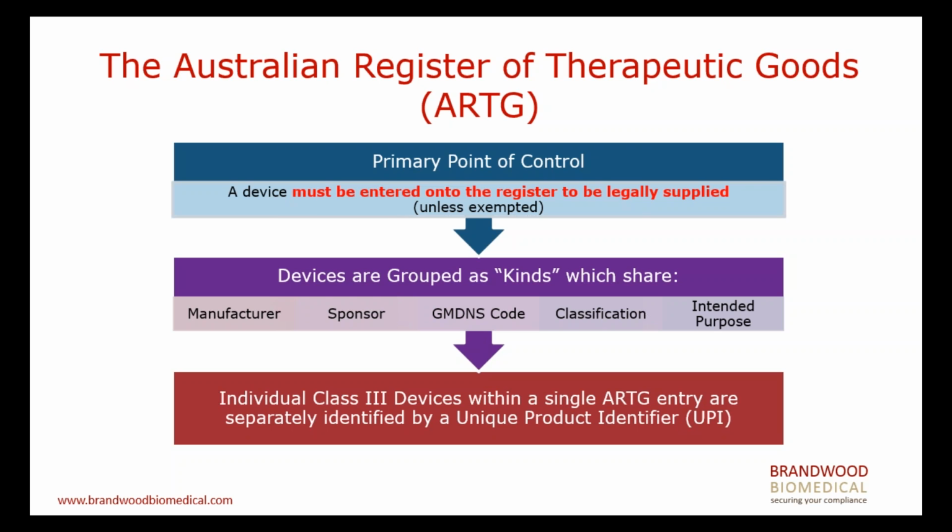And the key thing here is when you try and supply a product, they can actually be grouped into one ARTG certificate. That's the second point in there. So devices can be grouped as kinds of devices if they share certain characteristics, as listed over there. If there are any devices that have the same manufacturer, the same sponsor, GMDN code, classification, or intended purpose, then they can be classified as the same kind, and you can have one ARTG certificate that covers multiple devices.